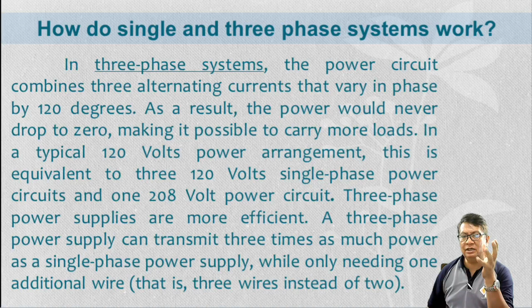A typical 120 volts power arrangement is equivalent to three 120 volts single phase power, so one 208 volt power circuit. This means that if we have a three phase system, then whatever the total power, it will be divided into three. If the power is divided into three, the current becomes smaller, considering that we have a constant voltage. When the current is smaller, the conductor we use can also be smaller. So for a bigger load, we should use the three-phase system. For a smaller load, use the single-phase system.